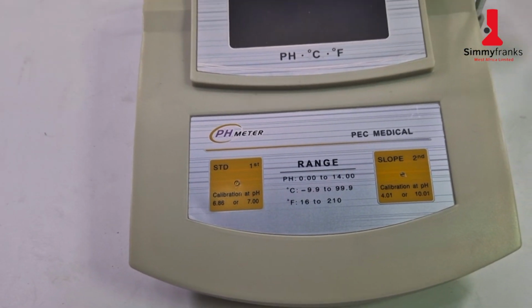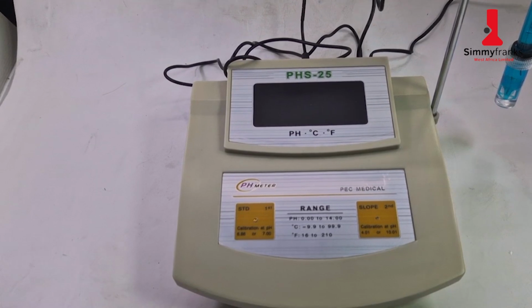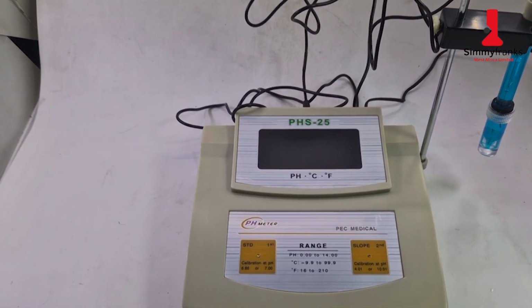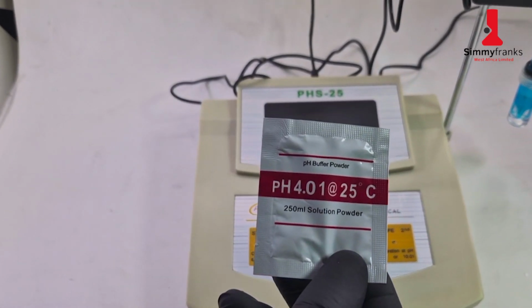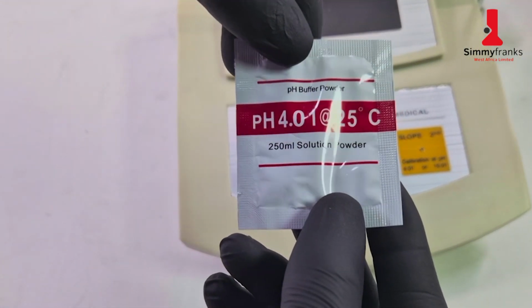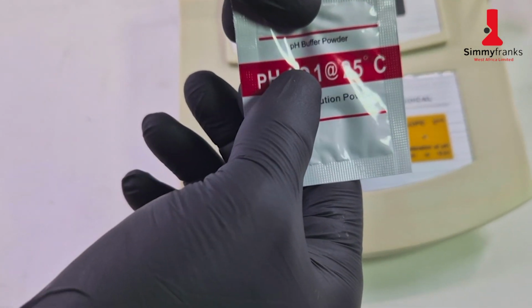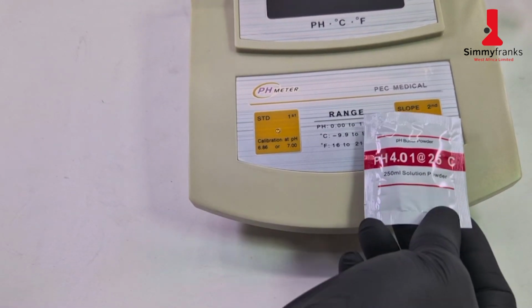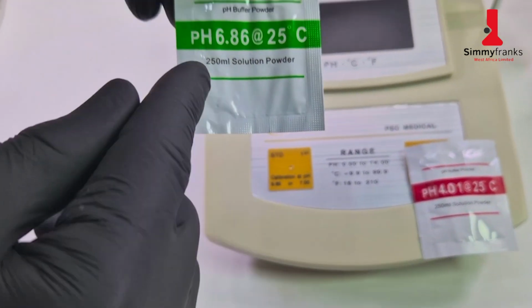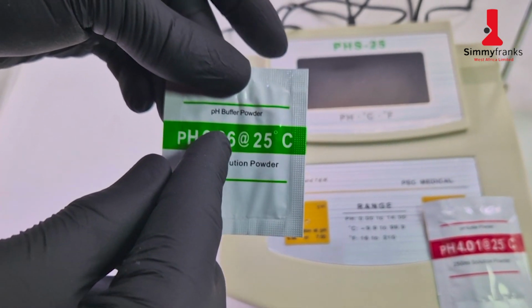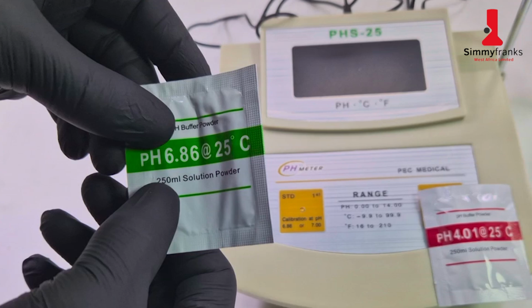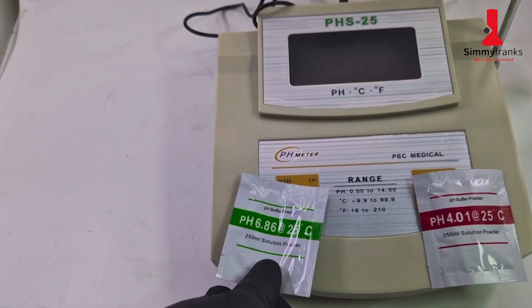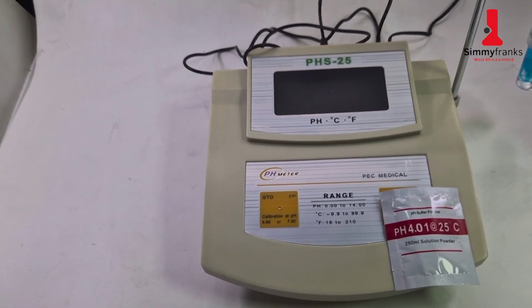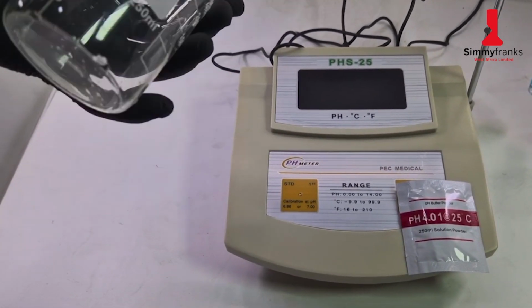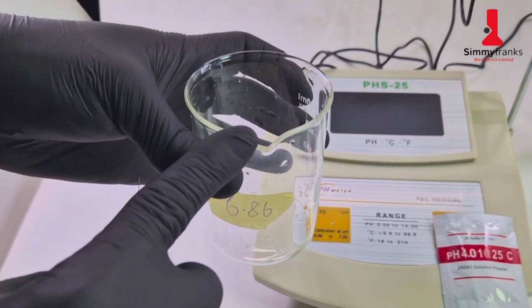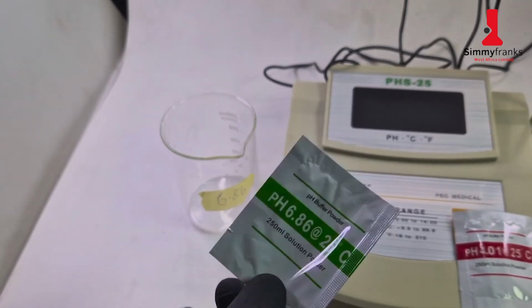7.00. So for you to calibrate, you have to have your solutions which you use to do your calibration, and for those solutions you need your buffer powders. So we are going to dissolve this pH 4.01 powder to be able to calibrate for 4.01, and also we are going to dissolve pH 6.86 powder in 250 milliliters solution water, for these two. So we are going to do that now. I'm going to get my glass for my 6.86. So I'm going to be using this glass to dissolve 250 milliliters of this.